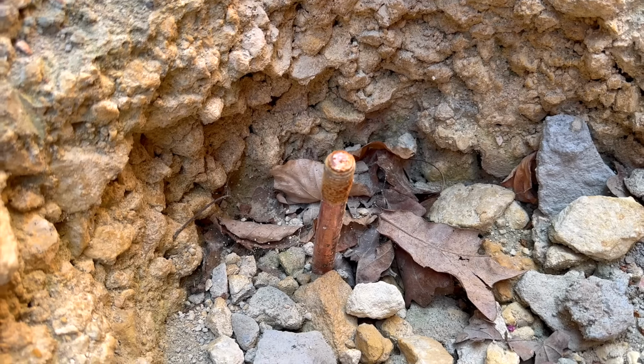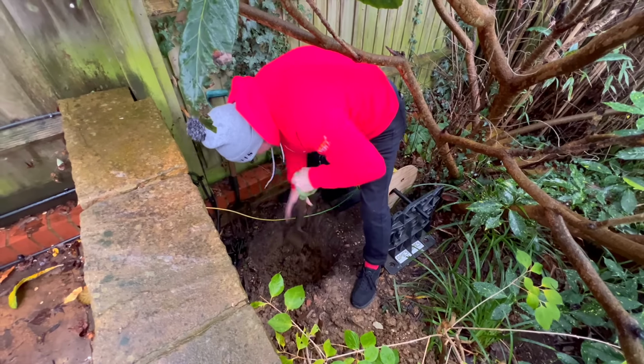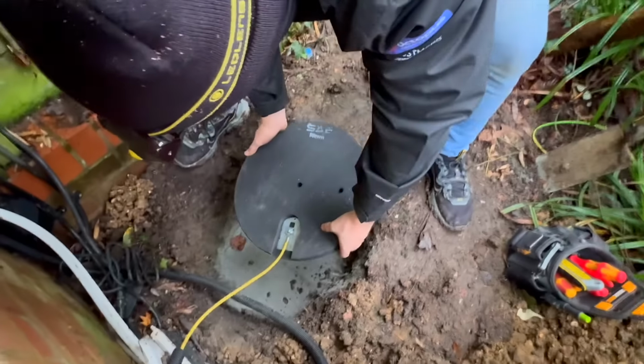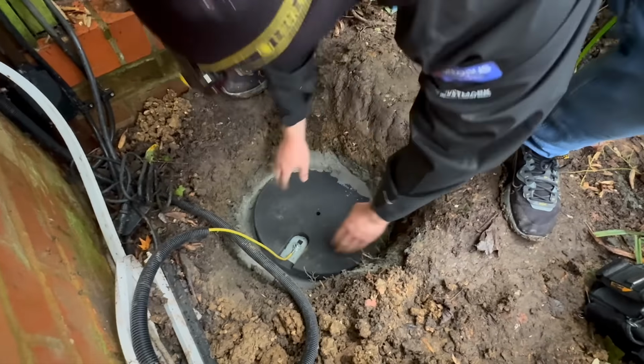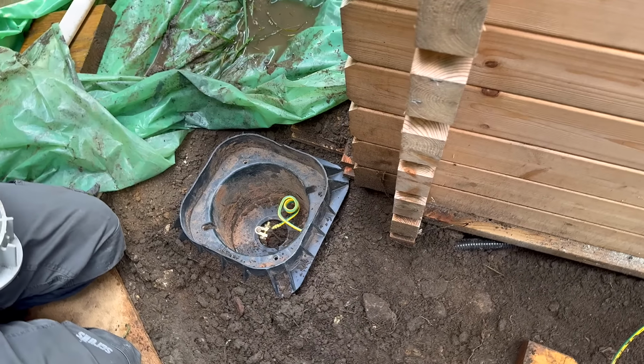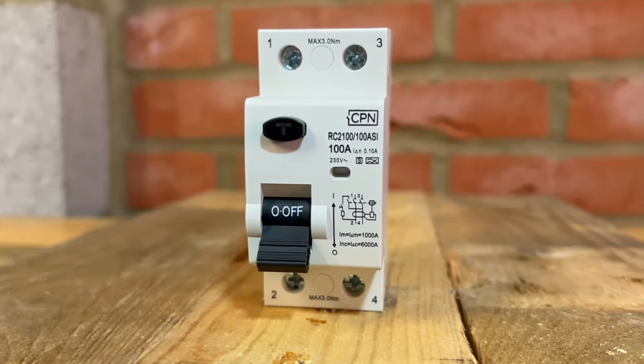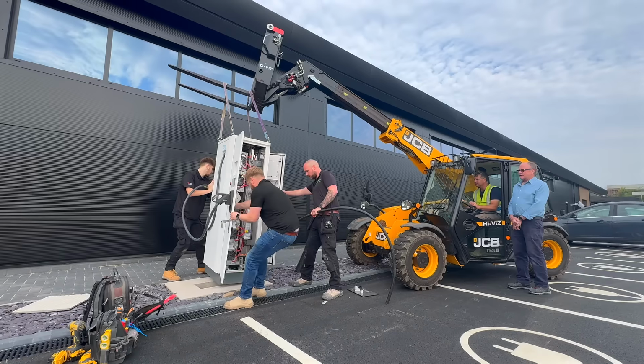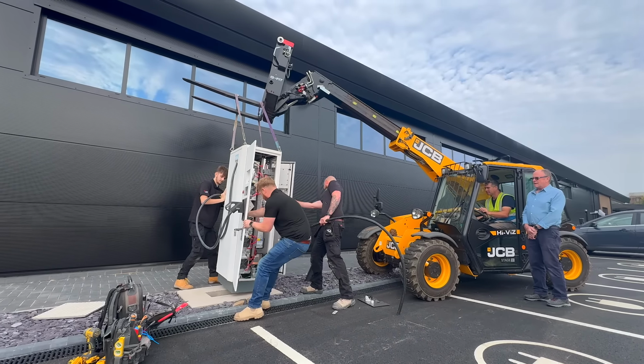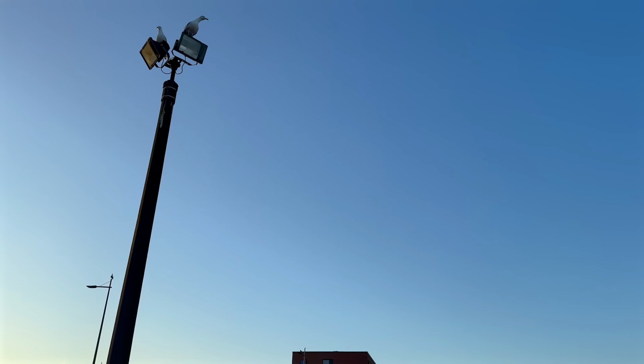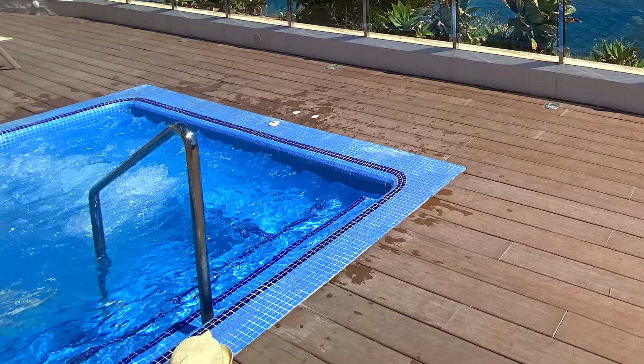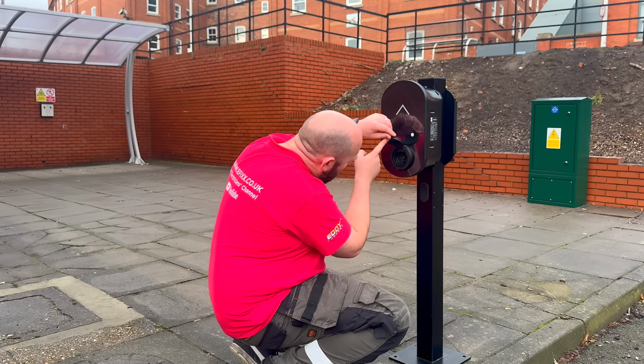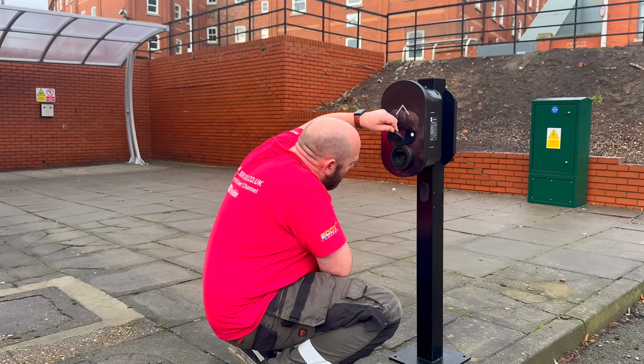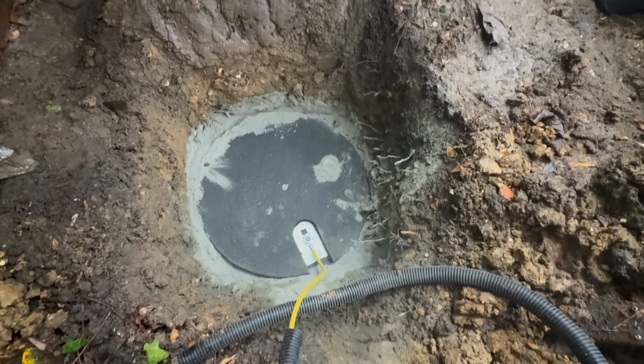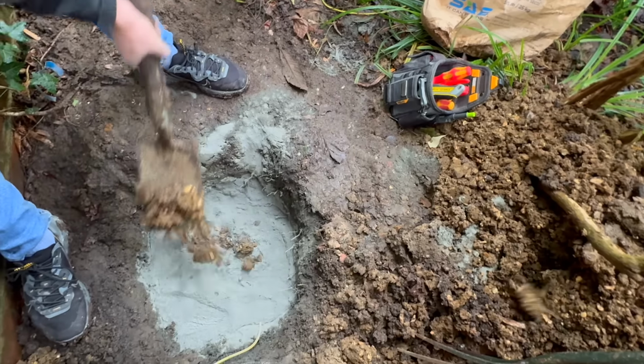So this is where we use a TT. By using a local earth electrode, the installation is no longer reliant on the supply neutral for fault clearance. Instead, fault current is limited and controlled through the earth electrode and protective devices, typically RCDs. That separation is the reason TT systems are used in specific scenarios. Street lighting columns are a good example, so are hot tubs and outdoor pools. Some EV charger installations also use a local earth electrode. In each case, the common factor is contact with the ground and accessible exposed conductive parts.